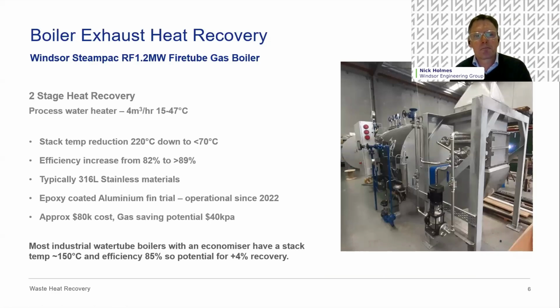So this is a major food and beverage player in New Zealand, on the back of a fire tube boiler, a 1200 kilowatt gas-fired boiler. A little bit special. There were some real constraints on physical footprint, so the heat recovery coil was mounted vertically with a stack sitting above it. We recovered heat from the 220 degrees stack temperature using low temperature process water at 15 degrees. We could drive that stack temperature down to 70 degrees. So it was not fully condensing, but there's a lot of condensation happening in that flue gas stream.